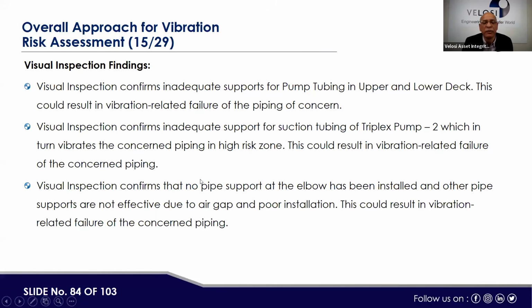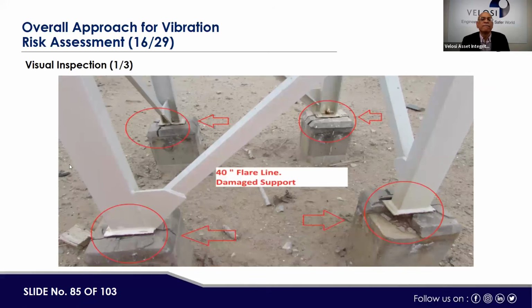Visual inspection confirmed that no pipe support at the elbow has been installed and other pipe supports are not effective due to air gap and poor installation. This could result in vibration-related failure of the connected piping. Now here is one of the examples where, due to vibration in the structural support, we could see cracks appearing in the supports, which is a 40-inch flare line damaged support.